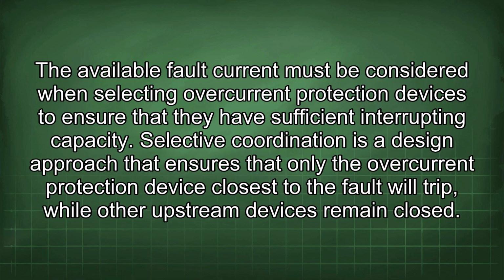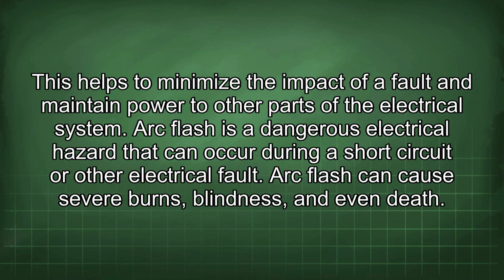The available fault current must be considered when selecting overcurrent protection devices to ensure that they have sufficient interrupting capacity. Selective coordination is a design approach that ensures that only the overcurrent protection device closest to the fault will trip, while other upstream devices remain closed. This helps to minimize the impact of a fault and maintain power to other parts of the electrical system.